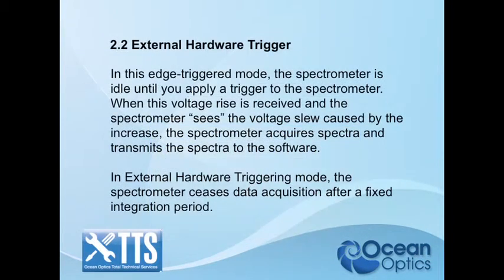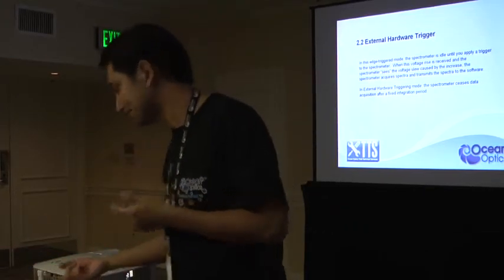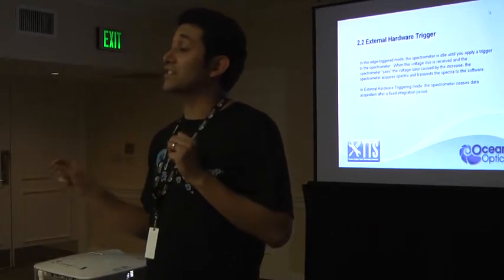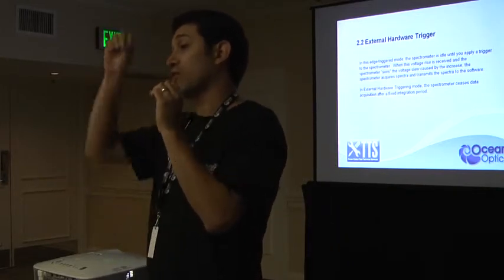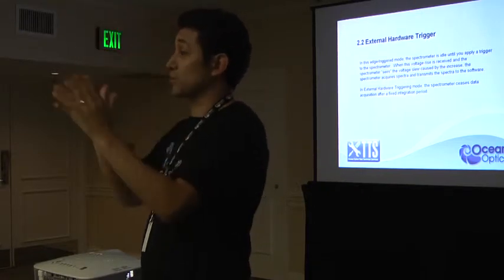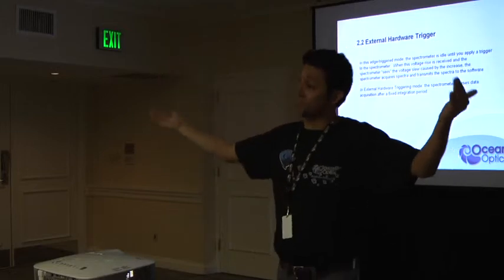External hardware trigger — this is an actual real trigger. In this mode, the spectrometer is completely frozen; it's not doing anything, just waiting for you to send the TTL signal. If you want to do very precise, time-critical acquisition, you use this mode. This is a rising edge trigger — every time you send a transition from zero to five volts, it acquires a new spectrum. If you need a hundred acquisitions, you need to send a hundred of those pulses.